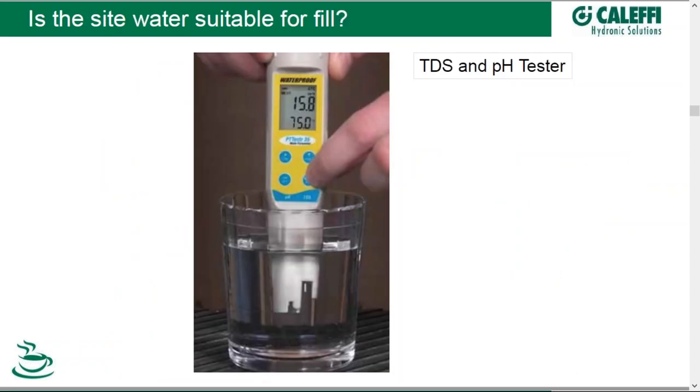Now we're ready to fill the system, and the question is: what are you going to fill it with? You might want to fill with a glycol solution for antifreeze, or with straight water. If you're filling with straight water, is the water available on site suitable for fill? Is it sufficient quality? A quick test using a TDS meter — such as the Caleffi one being demonstrated here, which also does pH testing — can help. When it comes to water quality for fill, TDS is your main measurement. pH is lesser so because in a hydronic system, pH values tend to stabilize.